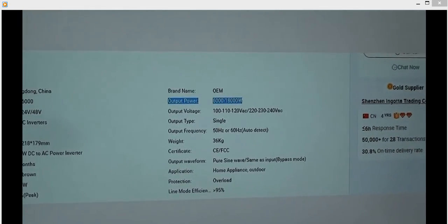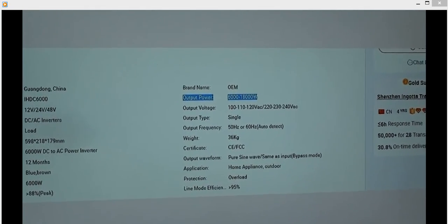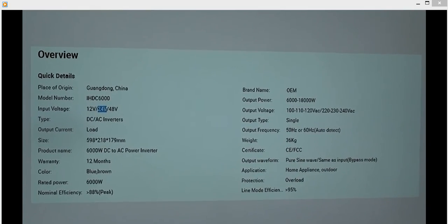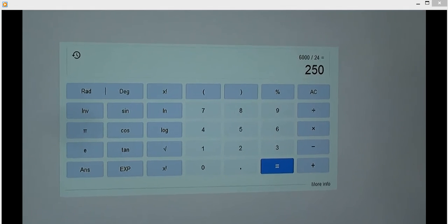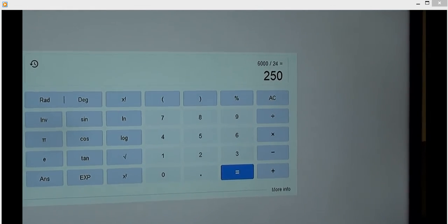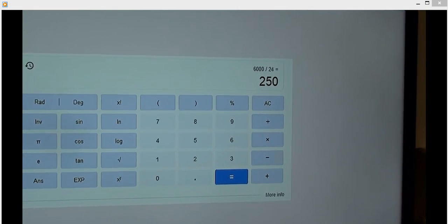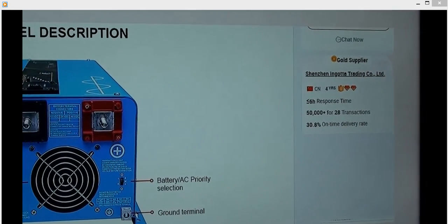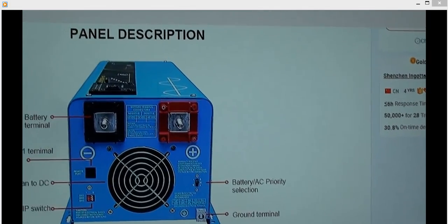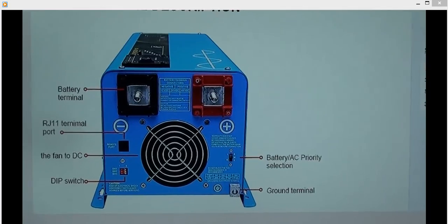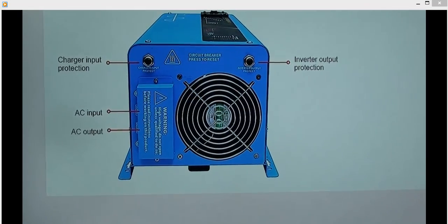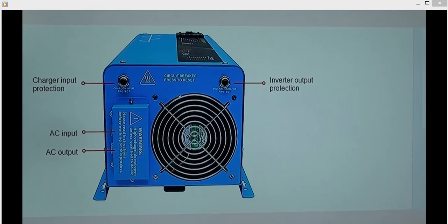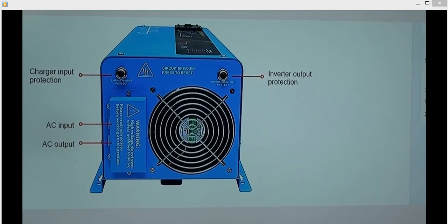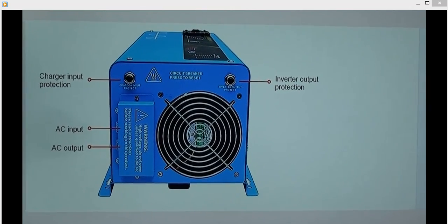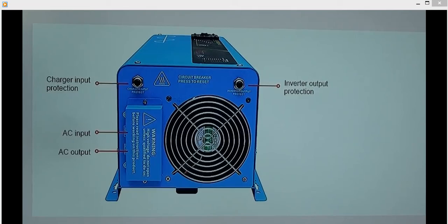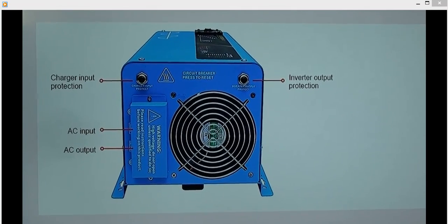And there's the output rating, 24 volts. You take 6,000 watts divided by 24, you come out with 250 continuous amps. It's the panel description for the DC side. And there's the panel description for the AC side, where you have your AC inputs if you hook it up to a camper cable, and you have an AC output going into the distribution box.